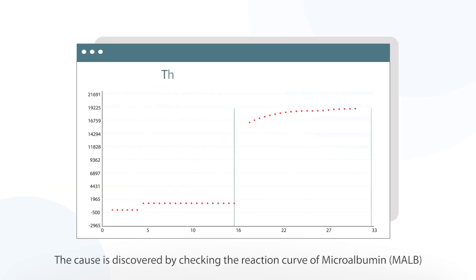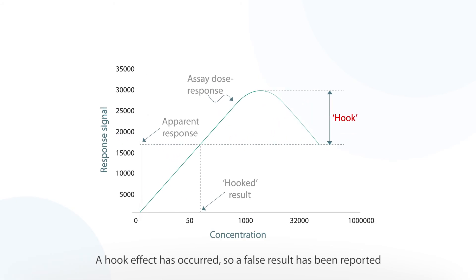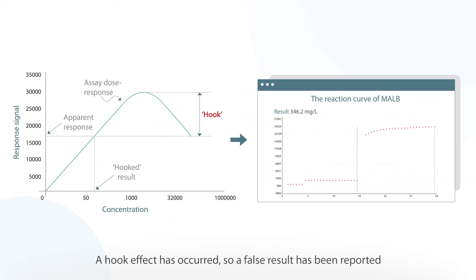The cause is discovered by checking the reaction curve of microalbumin. A hook effect has occurred so a false result has been reported.